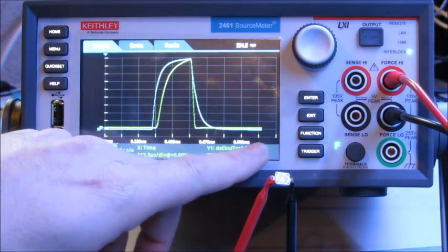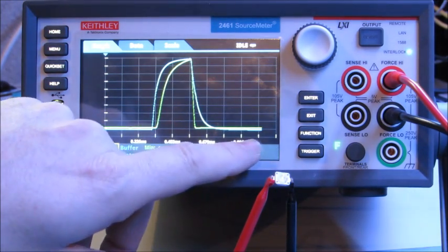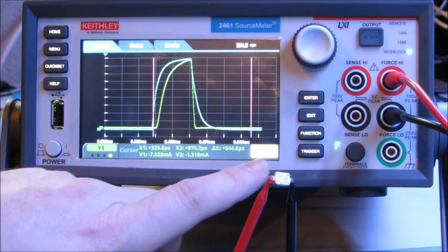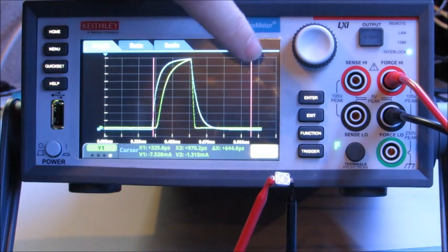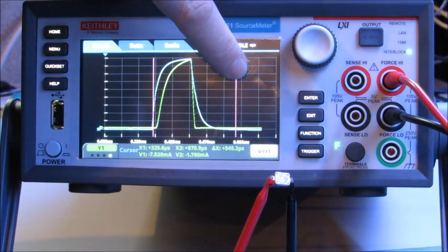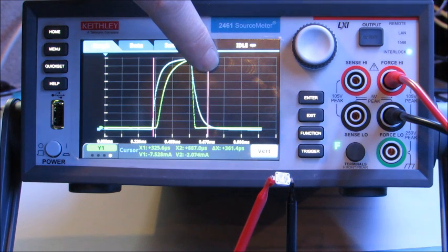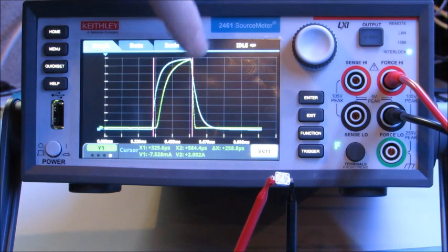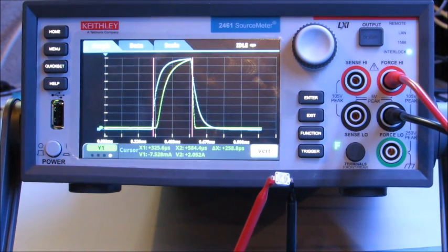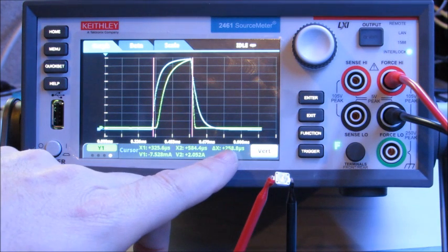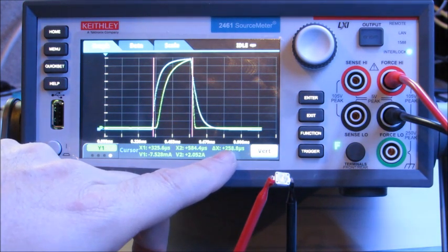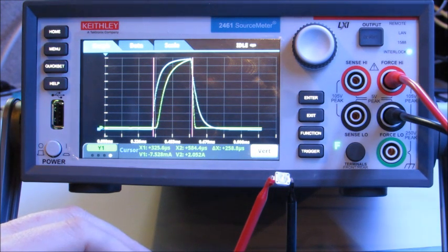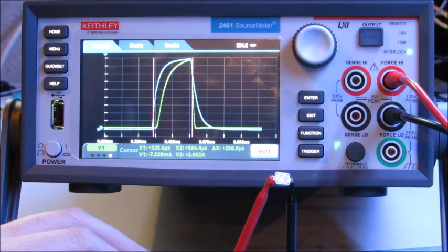And then if you're really interested in looking at things like the timing here, I can actually set up cursors here, vertical, and I can actually check the voltage pulse to make sure it was within 250 microseconds. And I roughly have the cursors in the right place. And if I look right here, I can see Delta X is 258.8 microseconds. So indeed, the 2461 was outputting a voltage pulse at 250 microseconds.